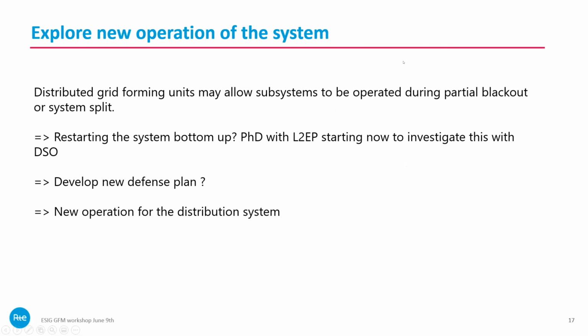With grid forming, we also need to explore new operation of the system—especially distribution system operation. For now, distribution operators just want distributed units to trip when there is an issue on the system. Now with a grid forming unit, they can in fact be operated in island, allowing subsystems to be operated during partial blackout, while presently they would probably be blacked out too.